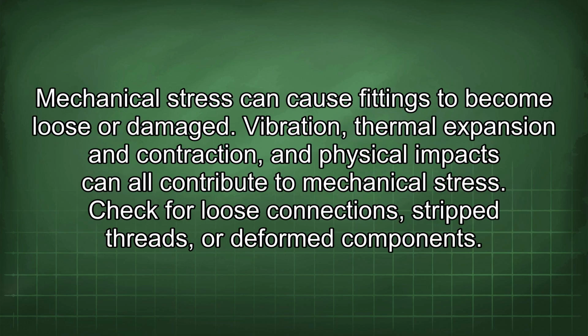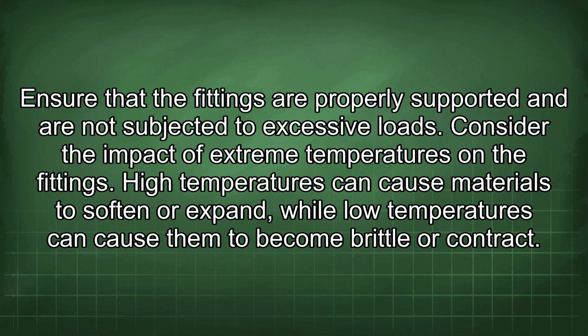Mechanical stress can cause fittings to become loose or damaged. Vibration, thermal expansion and contraction, and physical impacts can all contribute to mechanical stress. Check for loose connections, stripped threads, or deformed components. Ensure that the fittings are properly supported and are not subjected to excessive loads.